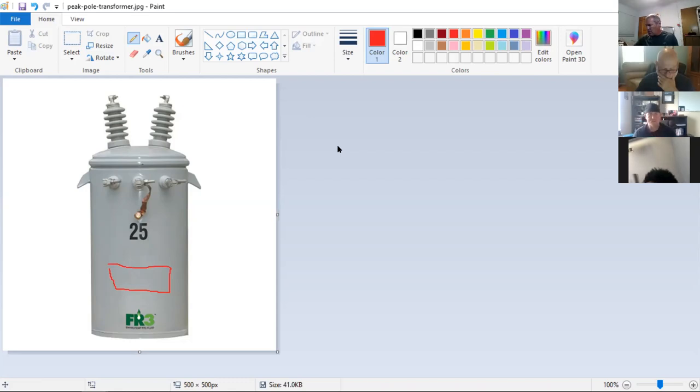I can simply call Santee Cooper and say, I'm at transformer 1, 2, 3, 4, can you run a load calculation on that transformer for me? And just sit back and eat a pack of crackers and drink a soda for a couple of minutes. They're going to come back and say, well, that transformer is running peak 40.2 kVA. Well, what's the problem? I got a 25. Right.